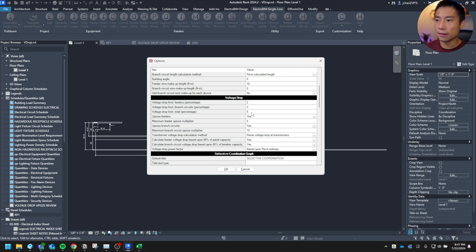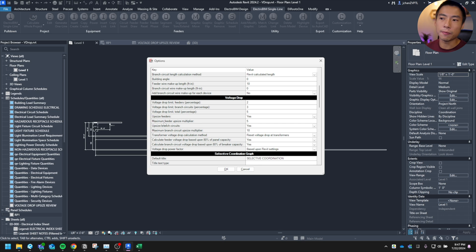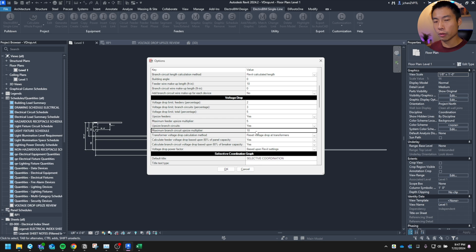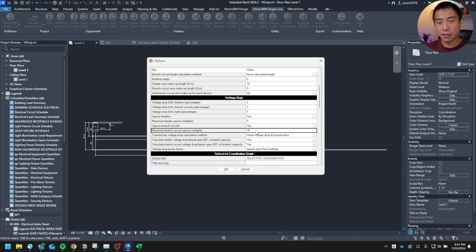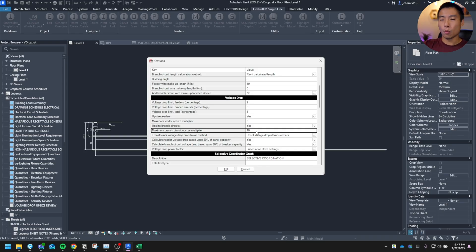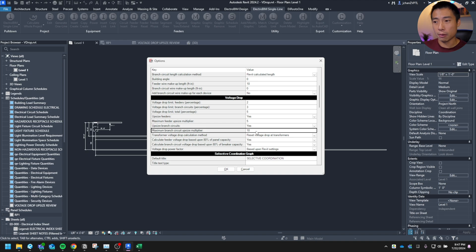And same thing here. You got your drop limit for feeders, branch circuit and total. So I have it set for two for feeders, three for circuits and five total. And then you can upsize feeders. Yes. There's a limit here, maximum feeder upsize multiplier. This is really cool because sometimes what Revit will do, will just keep upsizing until your percentage is met. So like, we actually had a problem where a receptacle was accidentally circuited to the wrong building and then Revit decided to upsize the wire. And it was like, hey, use a one-aught wire to run this circuit X amount of feet to the other building. And no one really caught that. It didn't like bring up an error or anything.